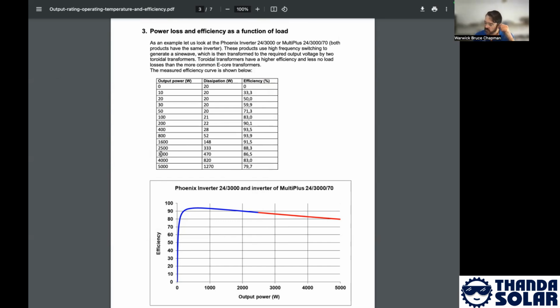And when it starts providing burst peak power for short periods of time above the 2.4 kilowatt sustained rating, then the efficiency goes down even further. So at a burst power provided of 5 kilowatts for a motor starting or something like that, that instant that the power is supplied, it's supplied at an even lower efficiency with a loss in excess of 20%.